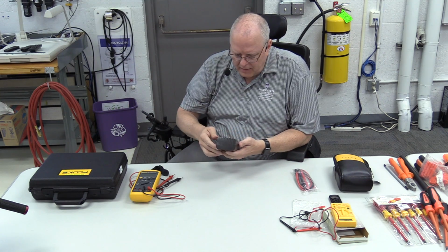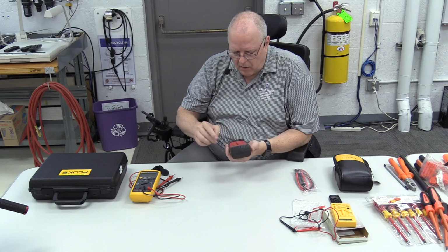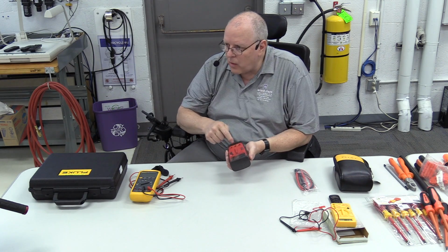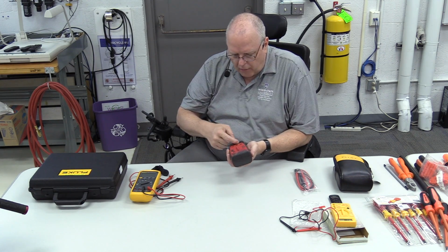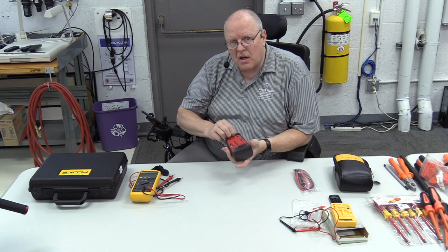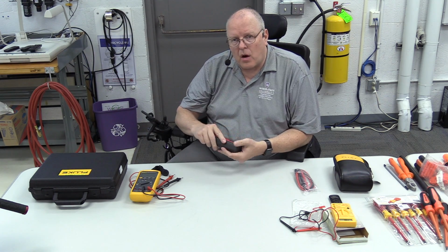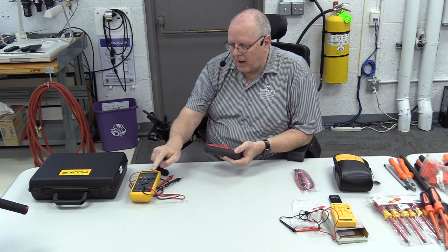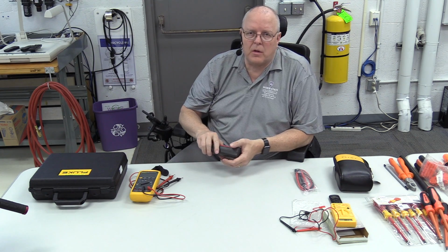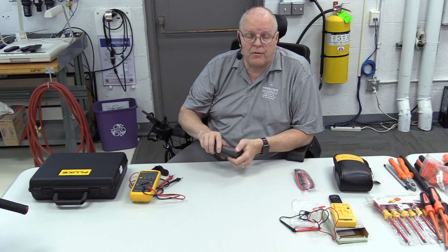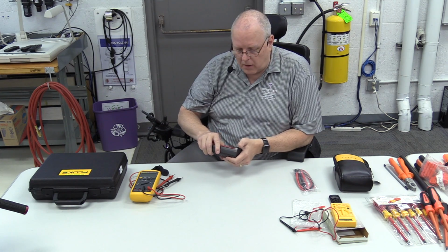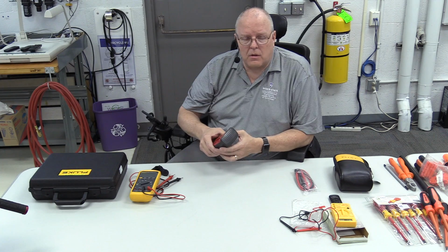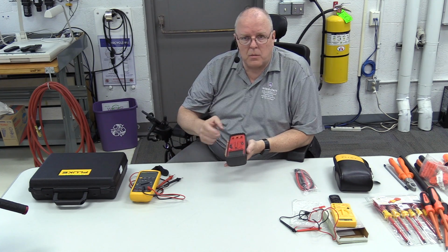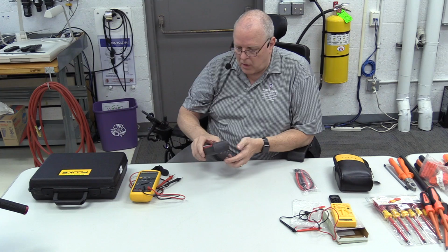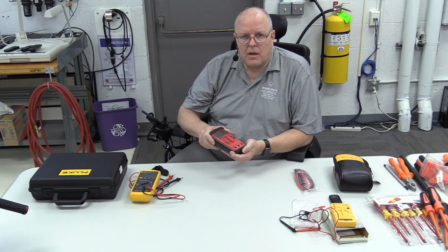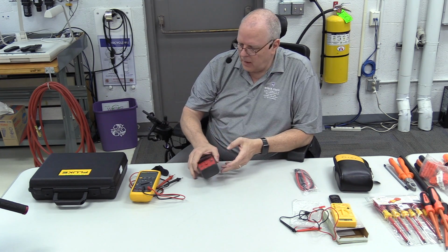So look at your multimeter. If it's not rated Category 3 on the front of the meter, chances are it's not Category 3. Now, there are some older Fluke meters that don't have any category listed on the front, but if you look up the owner's manuals online in a PDF document, it'll tell you that some were actually Category 3, some were Category 2, and so on. Find your owner's manual when in doubt and see what it's rated for.